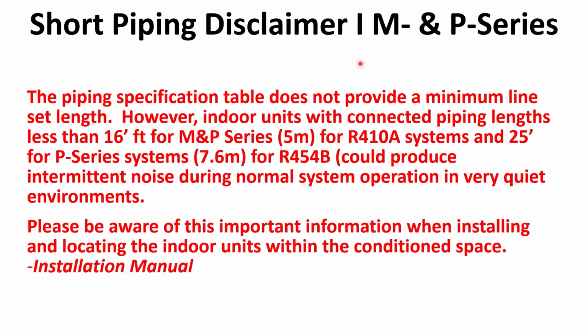And again, the short pipe disclaimer for our product. So again, it's talking about pipe. It doesn't provide a minimum length. However, indoor units connected with piping lengths less than 16 feet for the M and P series and 25 feet for the P series of R454B could produce intermittent noises during system operations. So again, just to prevent any type of refrigeration noises, then I would meet these requirements. So please be aware, important information when installing and locating the indoor units within the conditioned space. So yeah, noise, right? Noise related issues.